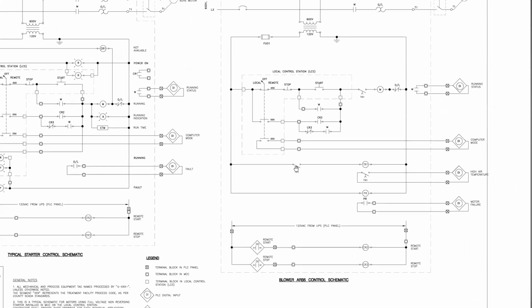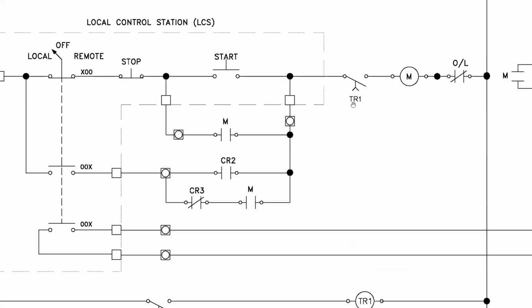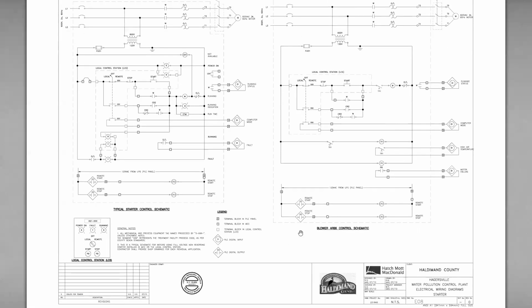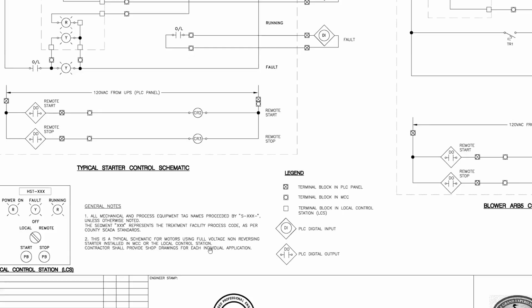When the temperature reaches a certain setting, TR1 will activate. TR1's a timer. However long the timer is set for, sometimes you will find here, here's the timer. It's going to wait to close on the end of the timer. Sometimes there will be like a 5S to indicate how long the timer is. That's a 5S, not a 55. So this could be set for 5 seconds or 5 minutes, or likely from an engineering drawing set, it will say something along the lines of timer settings to be set on site.